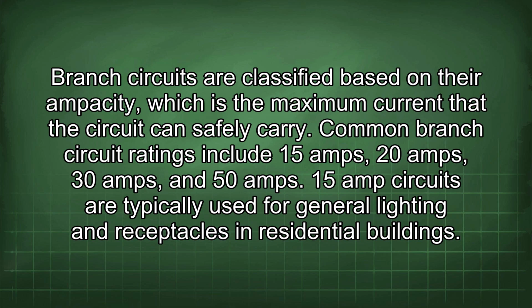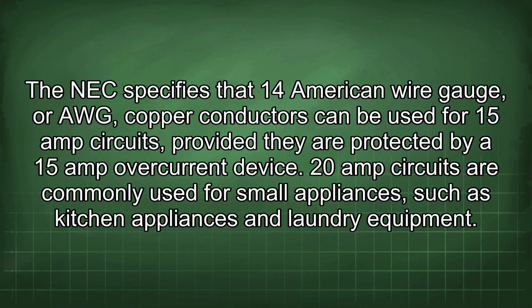Common branch circuit ratings include 15 amps, 20 amps, 30 amps, and 50 amps. 15-amp circuits are typically used for general lighting and receptacles in residential buildings. The NEC specifies that 14 American wire gauge, or AWG, copper conductors can be used for 15-amp circuits, provided they are protected by a 15-amp overcurrent device.